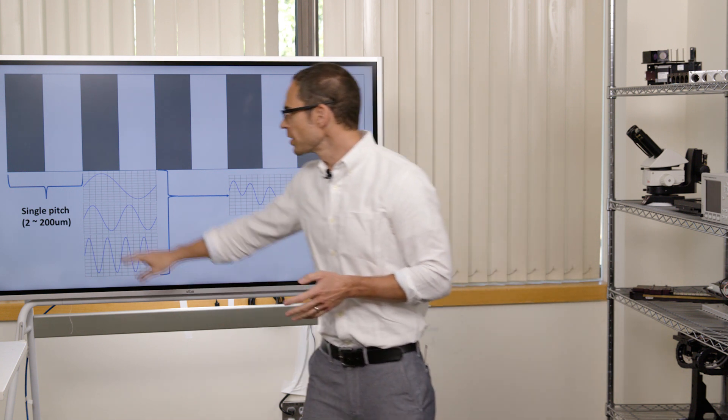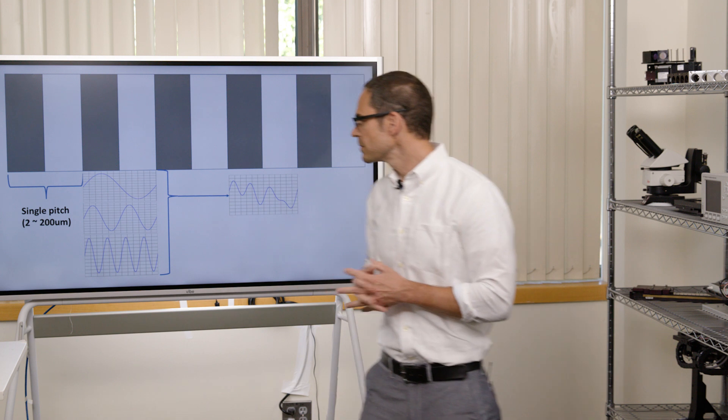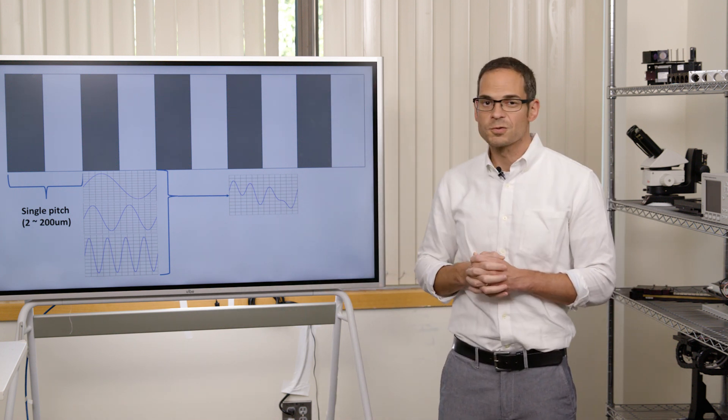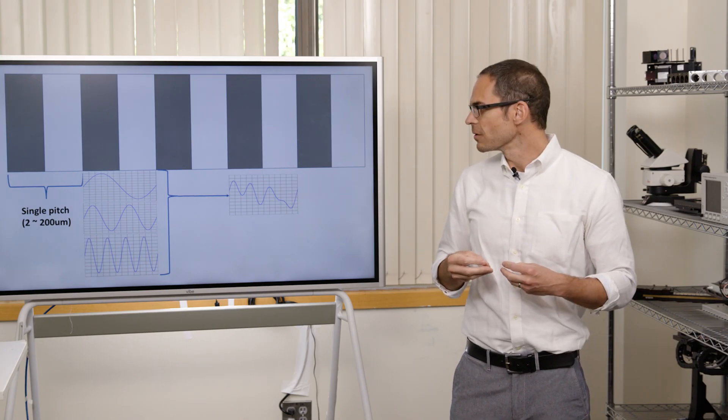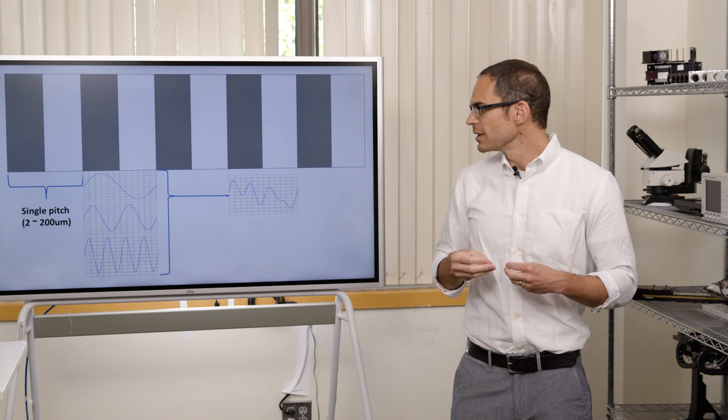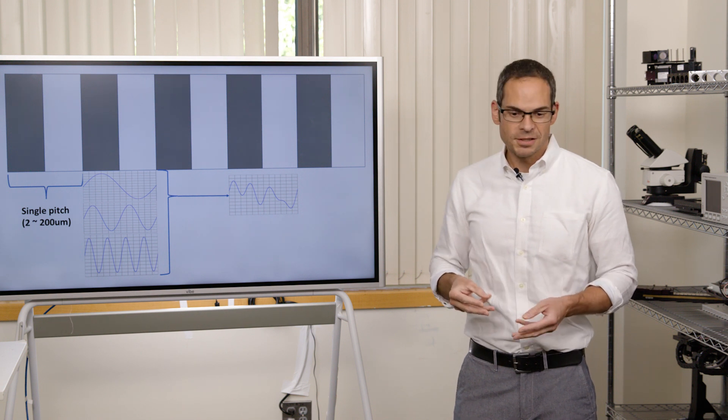So we call this a single pitch. Typically those are from two to roughly 200 microns. For us and for many encoders, that's about a 20 micron pitch. So we'll kind of take that as rule of thumb.